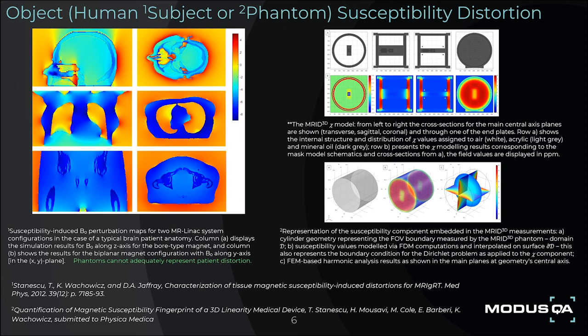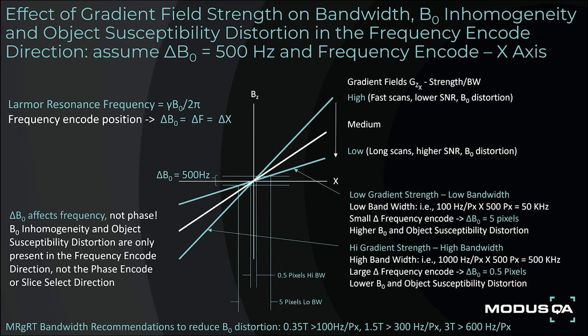Susceptibility-induced B0 perturbation maps of human subjects can be used to correct patient distortion, whereas phantom finite element models can be used to assign susceptibility values to air, plastic, and MR liquid contrast media to correct for phantom susceptibility distortion as a function of field strength, gradient strength, and frequency encode direction. Note that phantoms cannot adequately represent patient distortion. One of the simplest ways to manage geometric distortion arising from B0 inhomogeneity and object susceptibility-induced changes to B0 is to increase the gradient strength or bandwidth, which reduces the relative contribution to total distortion.